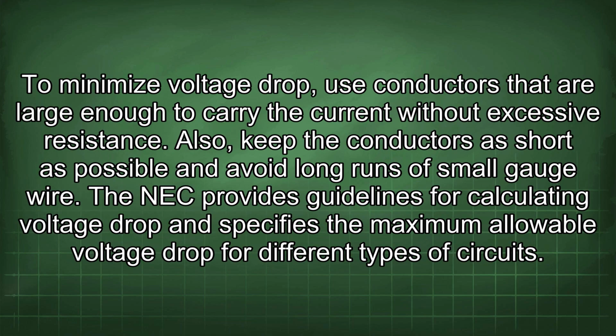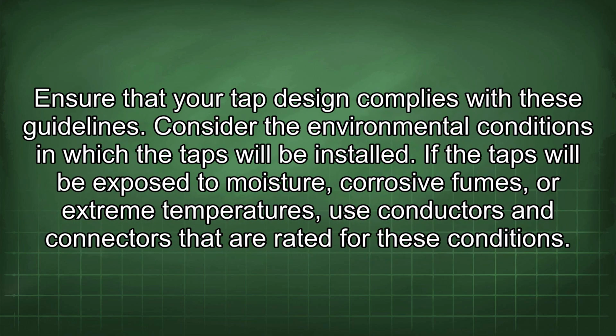To minimize voltage drop, use conductors that are large enough to carry the current without excessive resistance. Also, keep the conductors as short as possible and avoid long runs of small gauge wire. The NEC provides guidelines for calculating voltage drop and specifies the maximum allowable voltage drop for different types of circuits. Ensure that your tap design complies with these guidelines.